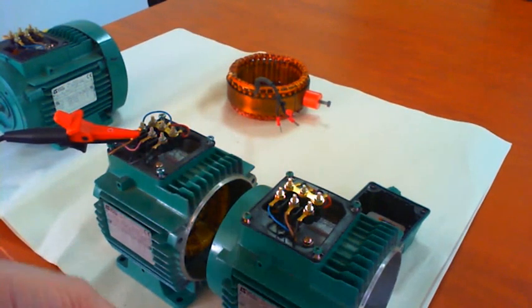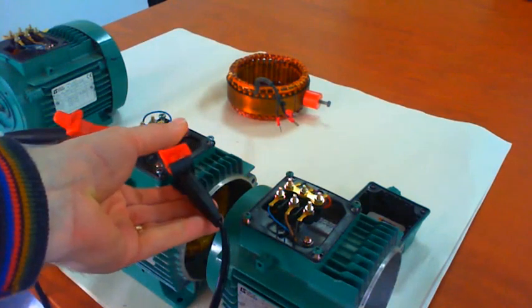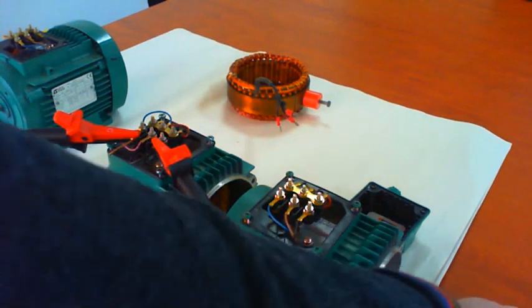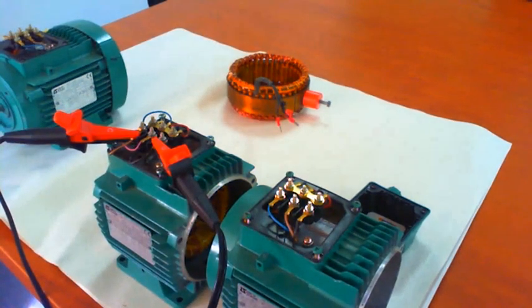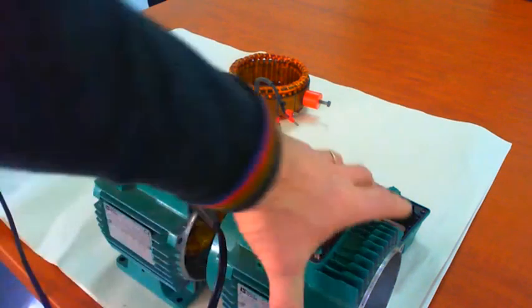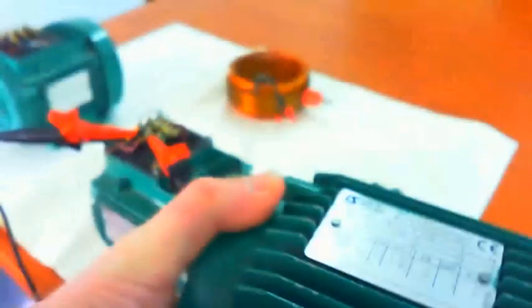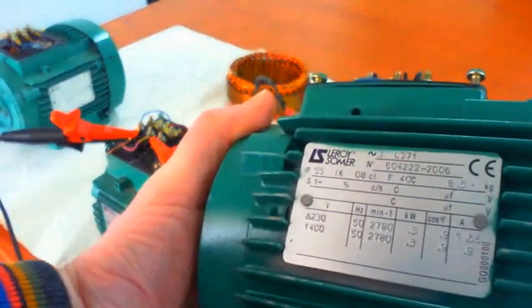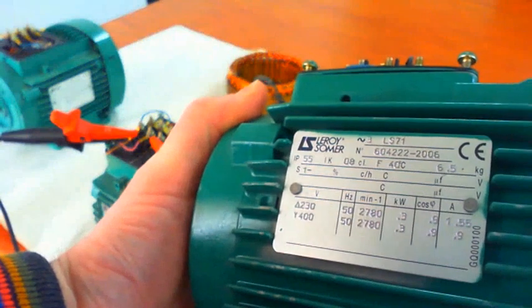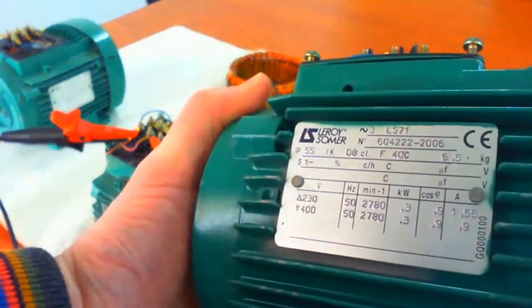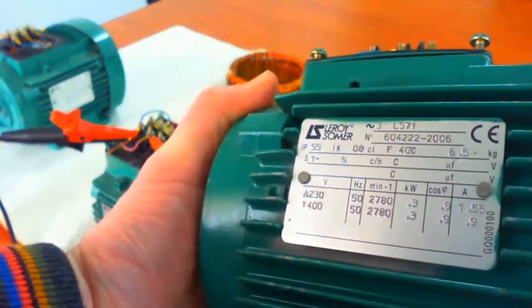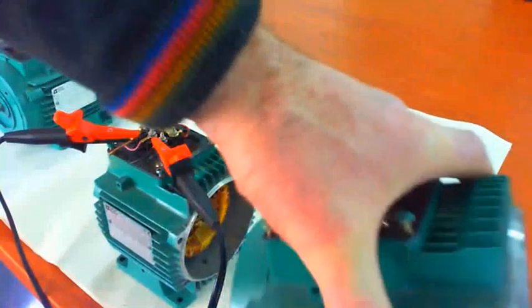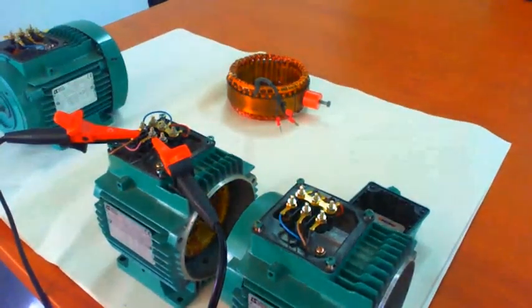It's not so easy with a very small terminal block. And then W to U, 46.4. So very similar values because the windings are the same design. And this is a 400 volt, 50 hertz, 0.3 kilowatt motor, and two-pole. Speed is 2,780 RPM. Okay, so that's resistance.